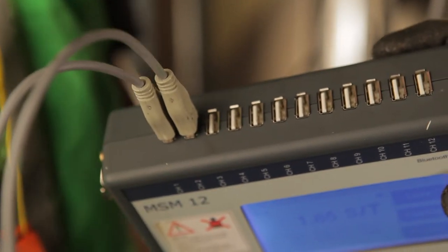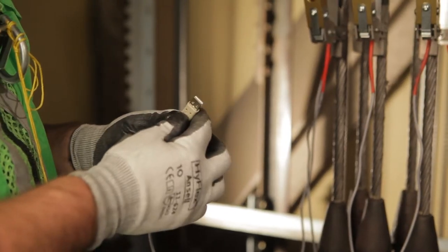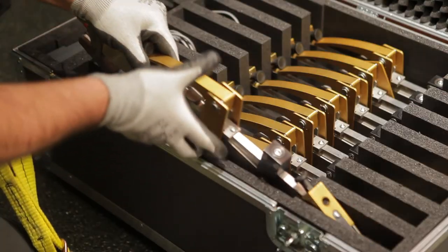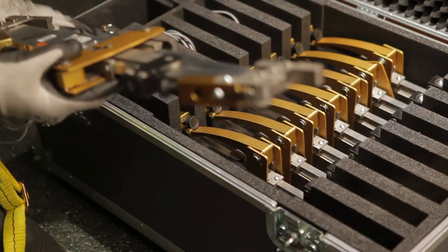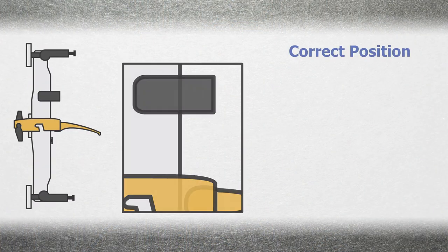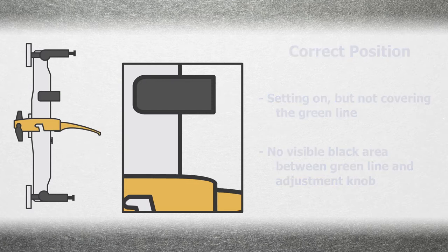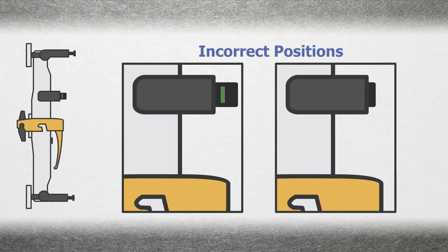When connecting the sensor to the MSM unit, make sure that the USB cords are attached and free of visible damage. The most important part of the measurement process is the attachment and setting of the rope sensors. The ideal goal is to achieve a setting on but not covering the green line in the middle with no visible black area between the green line and the adjustment knob.